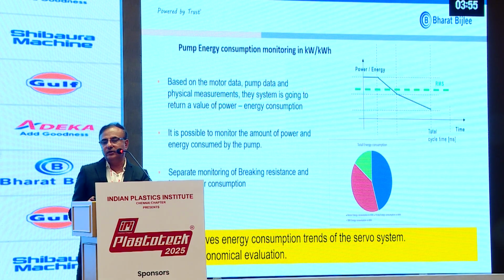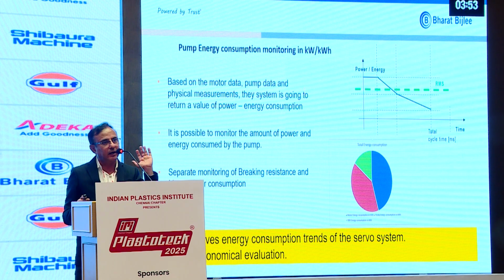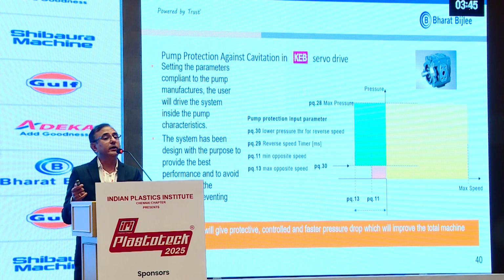We also have energy consumption shown directly on the drive - whatever energy is consumed by the pump and motor is directly displayed. It also has protection parameters for the pump against anti-cavitation, so the pump is protected against cavitation.